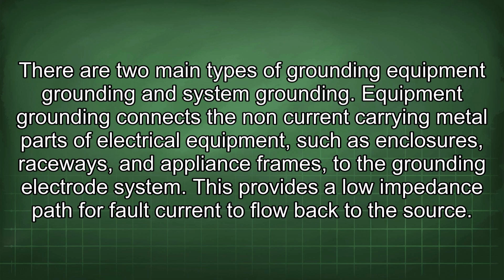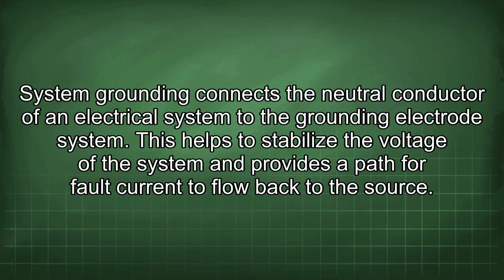Equipment grounding connects the non-current carrying metal parts of electrical equipment, such as enclosures, raceways, and appliance frames, to the grounding electrode system. This provides a low impedance path for fault current to flow back to the source. System grounding connects the neutral conductor of an electrical system to the grounding electrode system. This helps to stabilize the voltage of the system and provides a path for fault current to flow back to the source.